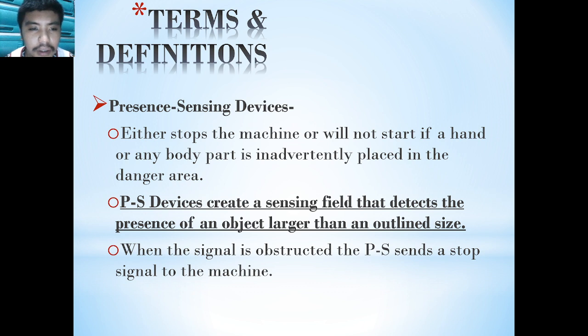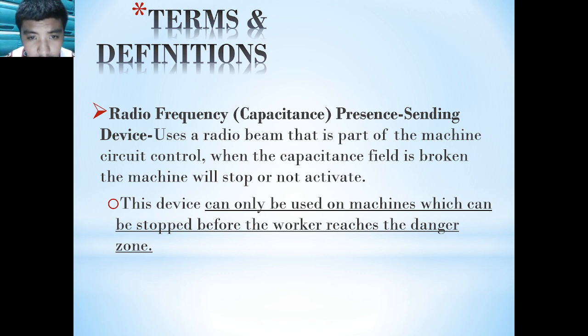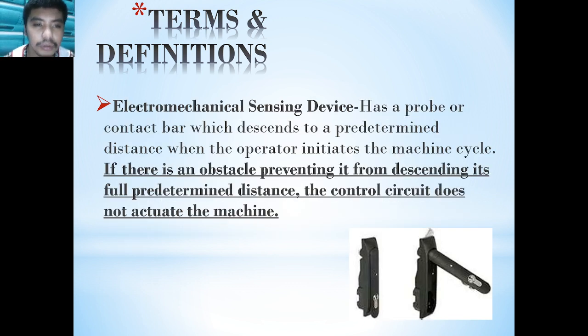Presence sensing devices either stop a machine or will not start if a hand or any body part is inadvertently placed in the danger area. These devices create a sensing field that detects the presence of an object larger than a defined outline size. Radio frequency capacitance presence sensing devices use a radio beam that is part of the machine circuit — when capacitance is broken, the machine will stop or not activate. This device can only be used on machines which can be stopped before the worker reaches the danger zone.